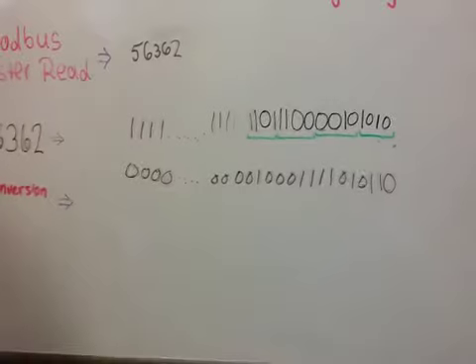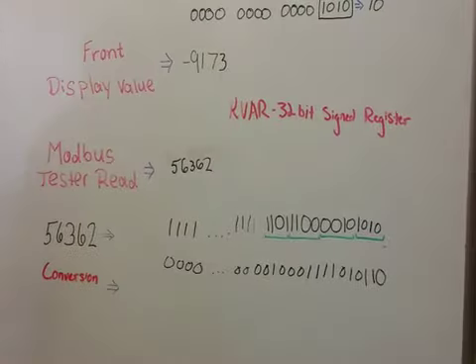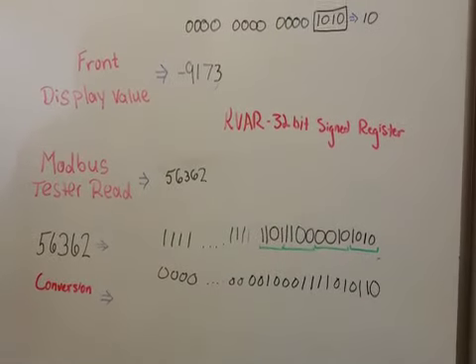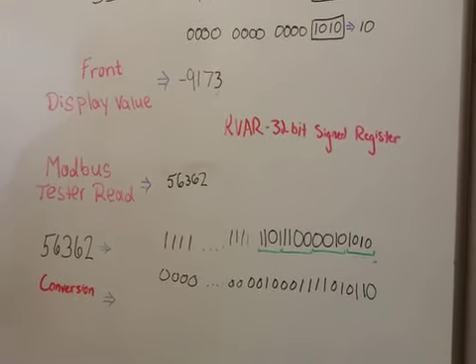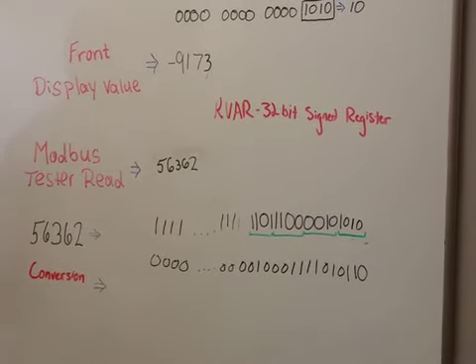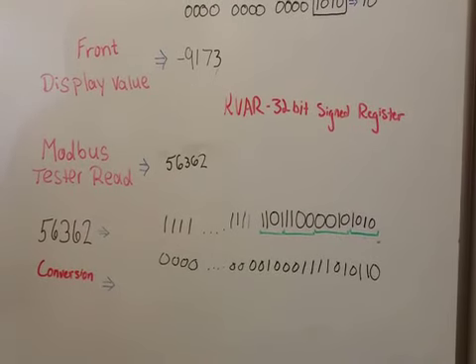And then once we read this value, it's going to read 9,173. And that's how we do the conversion between signed and unsigned, as well as Modbus Tester and EGX read a different number from the front display. And that's because they read it as an unsigned register.